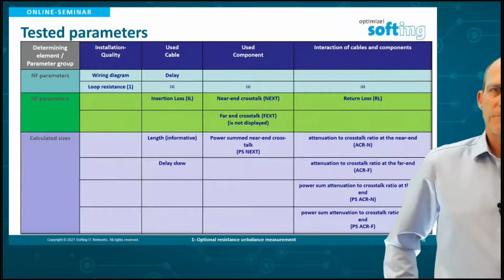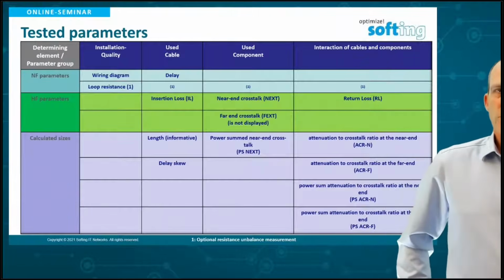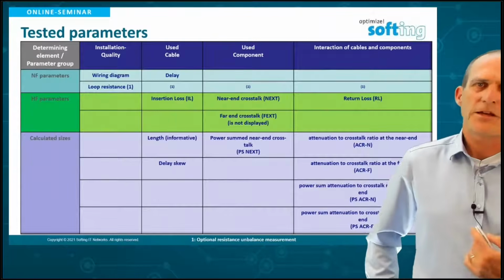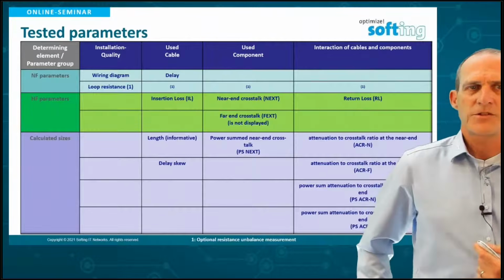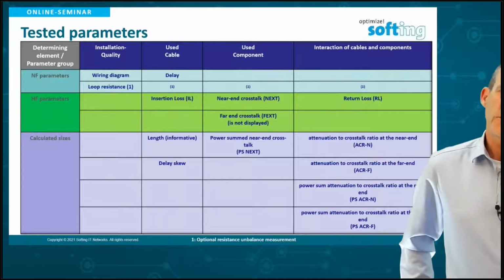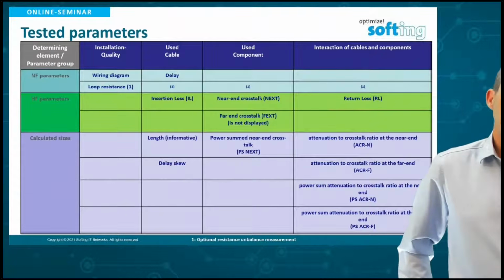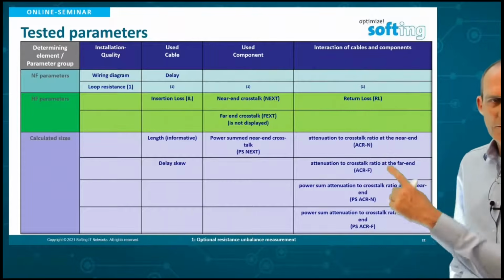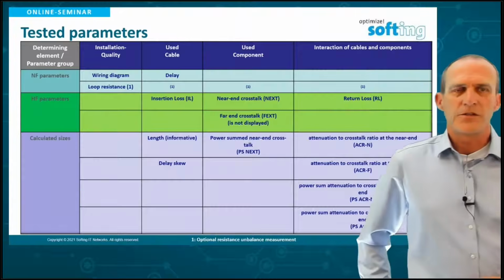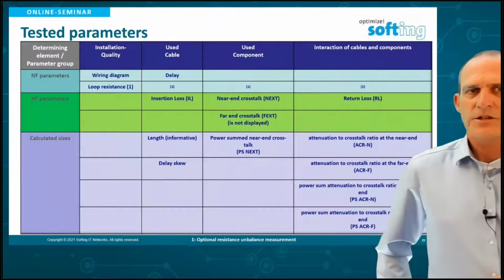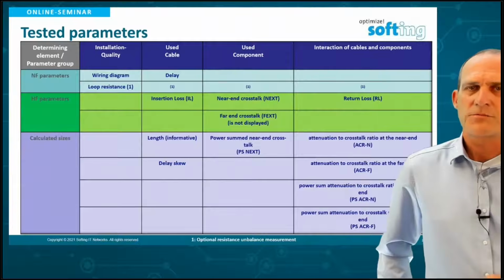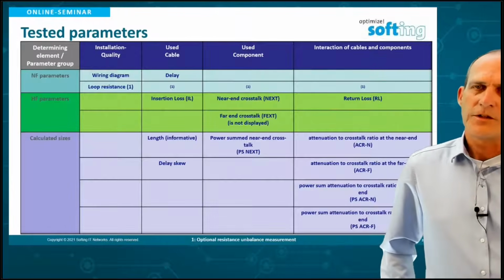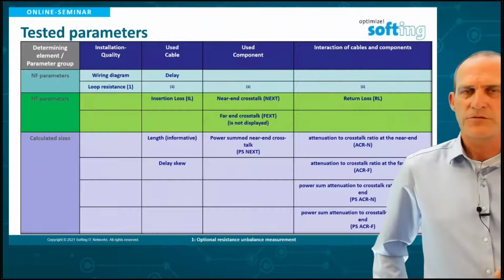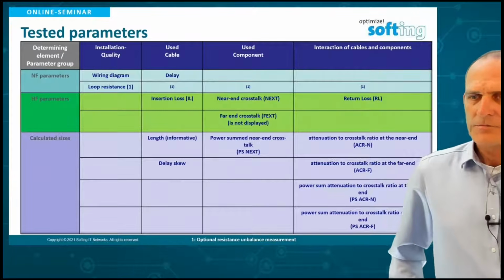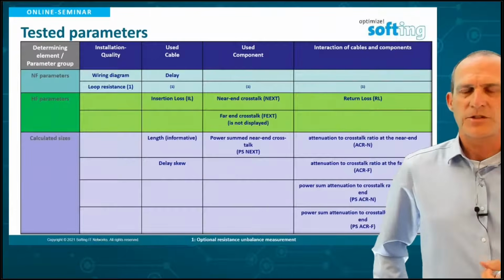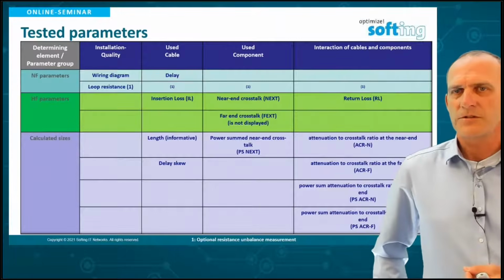Then we have a lot of high frequency parameters. Insertion loss gives you a clue if the cable is okay. Near-end crosstalk, far-end crosstalk is not displayed; it's used for calculating ACR and ACRF, as you see here on the side. NEXT basically gives you a clue on the connectors, if the connectors are good. Return loss basically gives you a clue about the interaction between the cable and connectors. Also, if you damage your cable during installation, return loss gives you a good clue when it has issues.